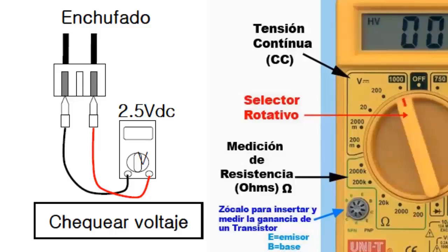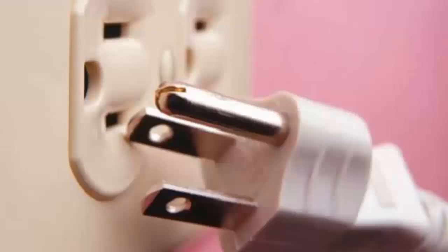5. Check the voltage supply that the board provides to the sensor. To do this, without disconnecting the sensor, measure the voltage at the sensor connection with a multimeter on the DC voltage scale. The voltage should be around 2.5 V.